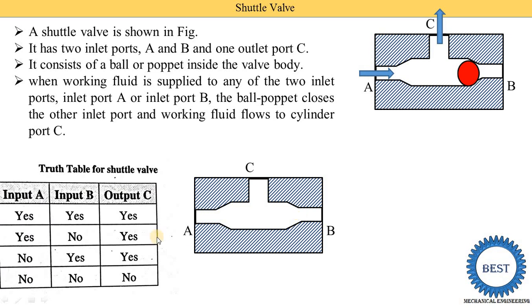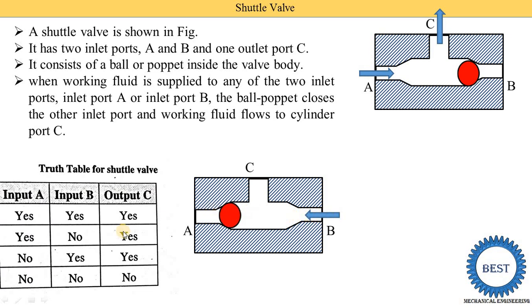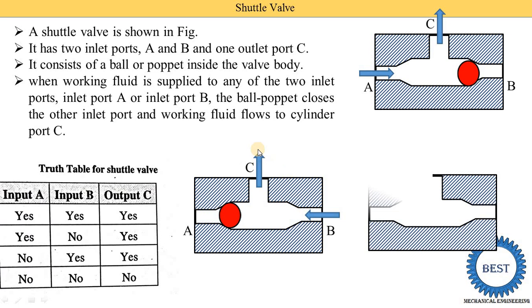Now for case three: fluid is supplied from inlet B. When we supply fluid from B, the ball moves towards the A port and A is closed. So in the truth table: input A is no, input B is yes, and output is achieved at C. Fluid entering at port B is directed to port C.